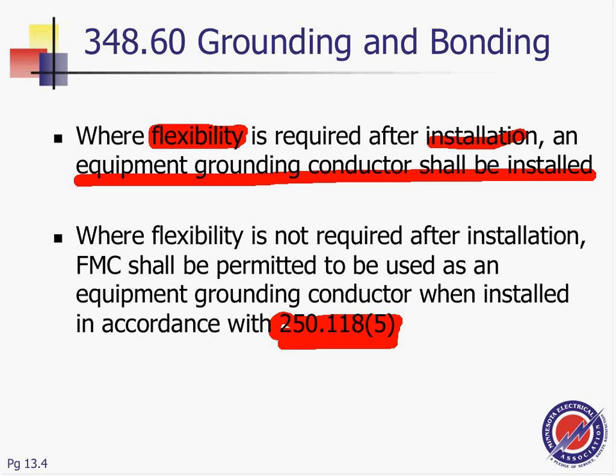And we're on it, guys. If you look underneath it, liquidtight flexible metallic conduit, the one that we're going to be seeing later. The same for metallic, okay, conduit protected by an overcurrent device. For liquidtight, guys, it's the same thing with listed fittings, and they give you a listed number of amps, all the way up to 60 amps. And 6 feet, the same thing. We'll use a connected equipment grounding conductor. So we'll get to that one in a second.